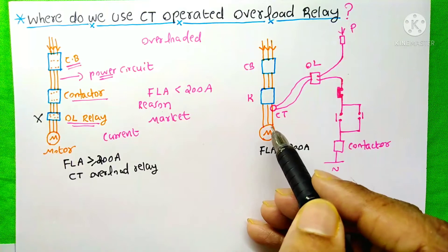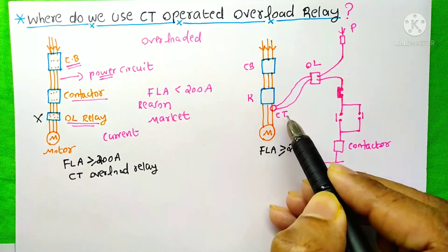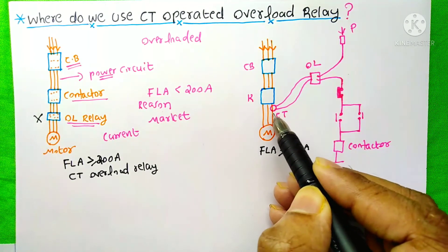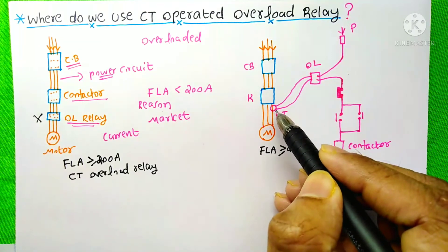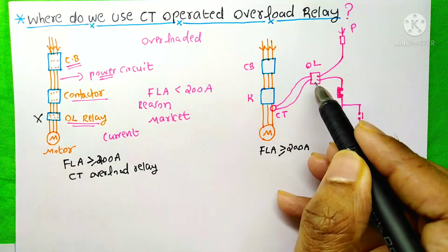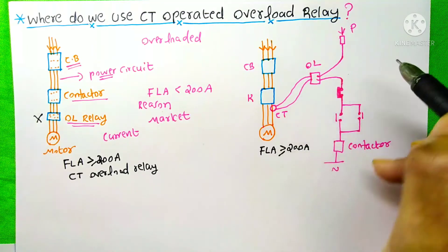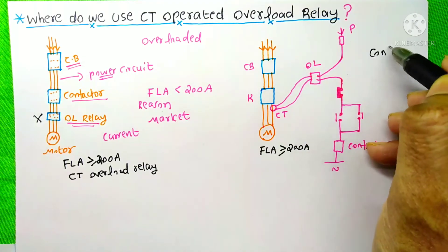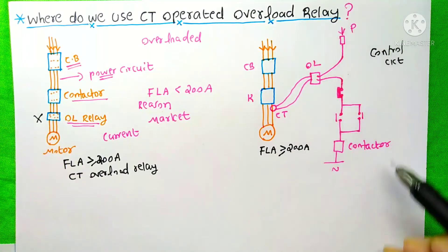So in this case, we use the current transformer in the power circuit, and we take the secondary wiring of this CT to the overload relay. This overload relay is on the control circuit, and it is the control circuit.